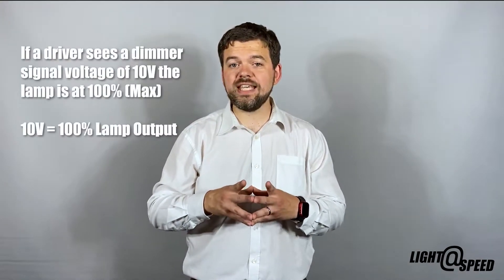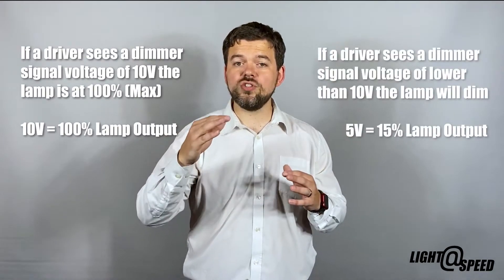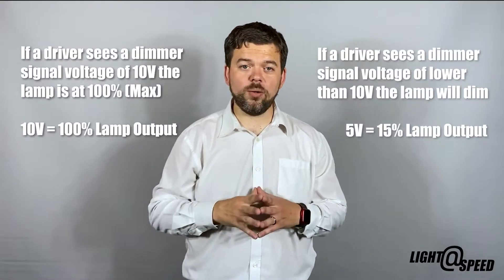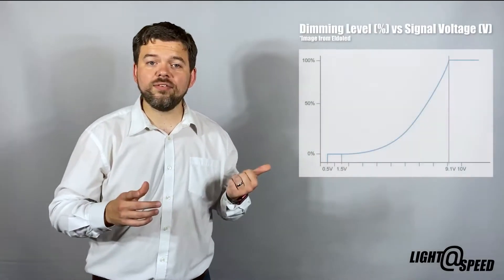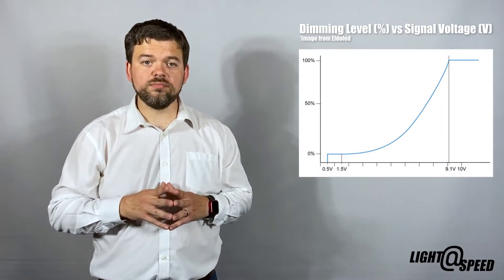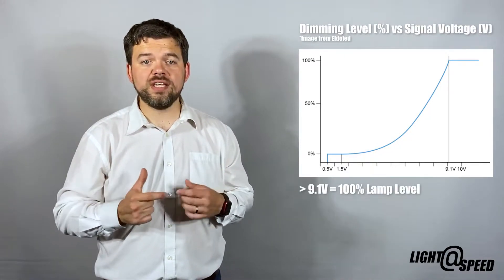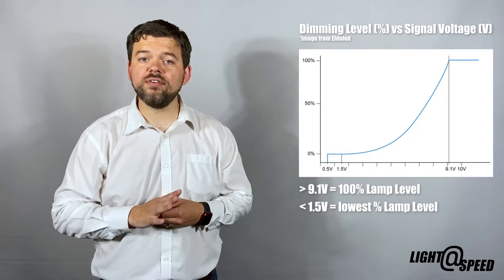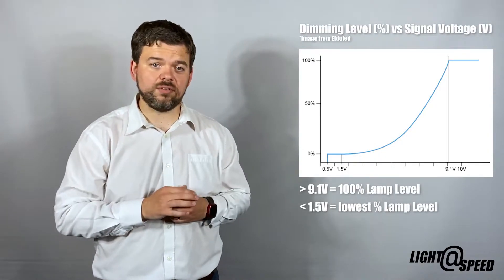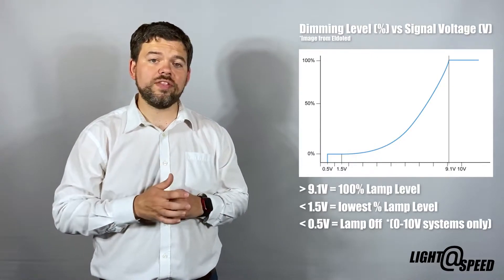When a driver or power supply sees 10 volts the lamp output will be 100%, and if it sees a voltage that's lower the output will be lower. Looking at a graph showing dimming level as a percentage against signal voltage level, any voltage above 9.1 volts causes the lamp to output 100%, and anything below 1.5 volts causes the lamp to be at its lowest level. For 0 to 10 volt systems, anything below 0.5 volts will turn the lamp off.